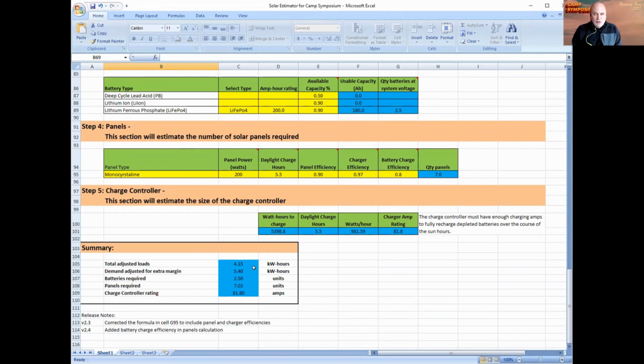Your total adjusted loads, 4.15 kilowatt hours. Demand with some margin, 5.4 kilowatt hours. Batteries required, 2.5, based on what you specified up above here. 7 panels, 7.03, but 7 is close enough. And an 80 amp charge controller. So here are all the parameters of everything you need to specify to build this system.